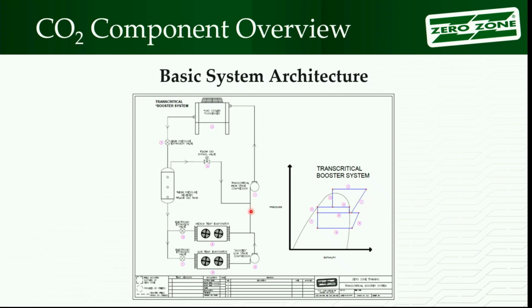We had a customer remoting into the store and they were having some low superheat alarms on the compressor. So we spent a lot of time, they had a lot of evaporators, looking at the superheat on the evaporators. Eventually we ruled those out and found that we were getting low temperatures. Actually, the low superheat was coming from the flash tank. Sent somebody in the store. They had filled up the system above the top sight glass with refrigerant. So they were vacuuming liquid refrigerant out of that receiver. So we got them to drop it down to the center sight glass. All is well. So just something to be aware of. You've got this extra stream that we're not used to seeing.